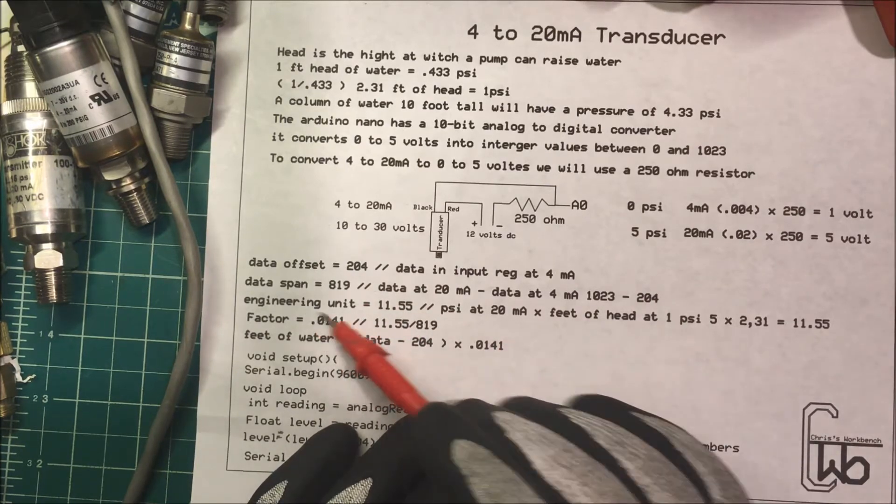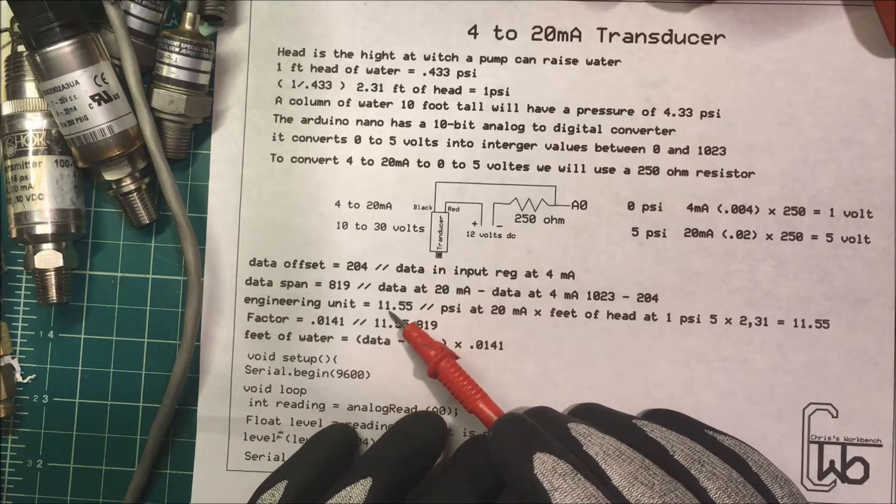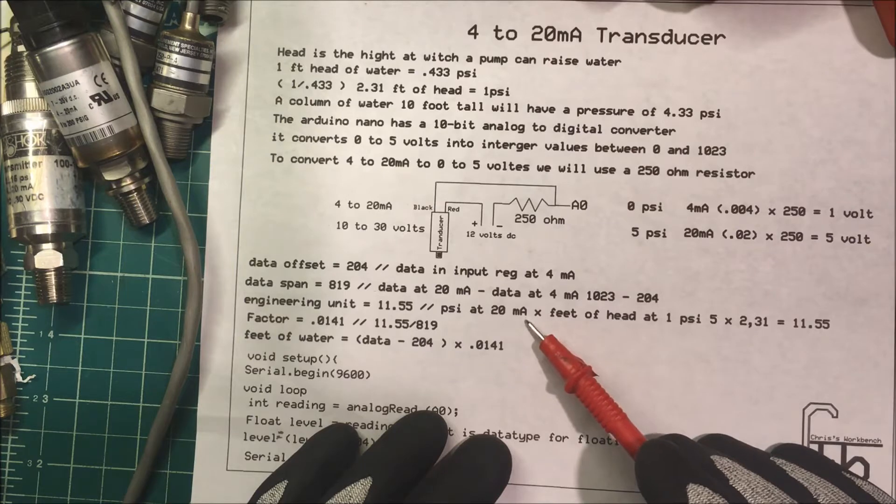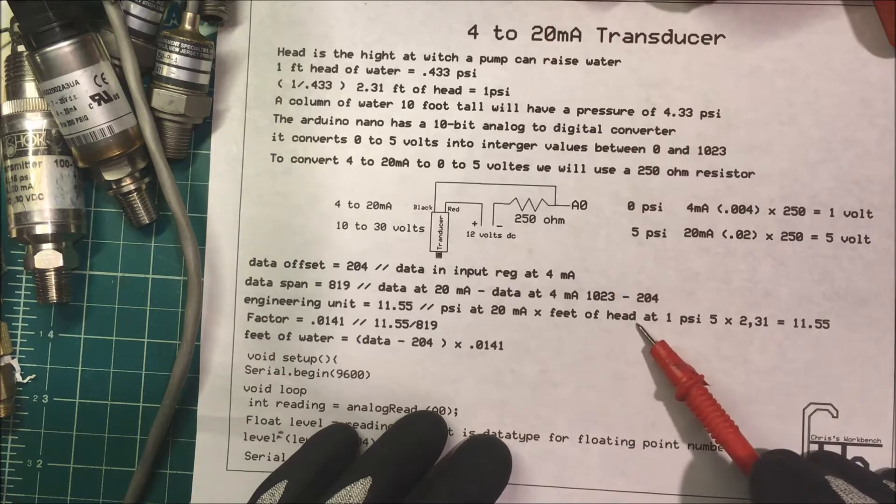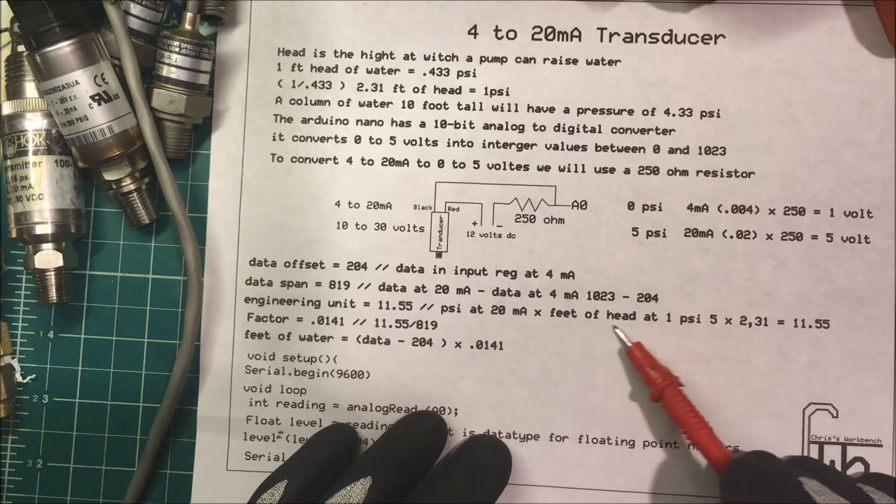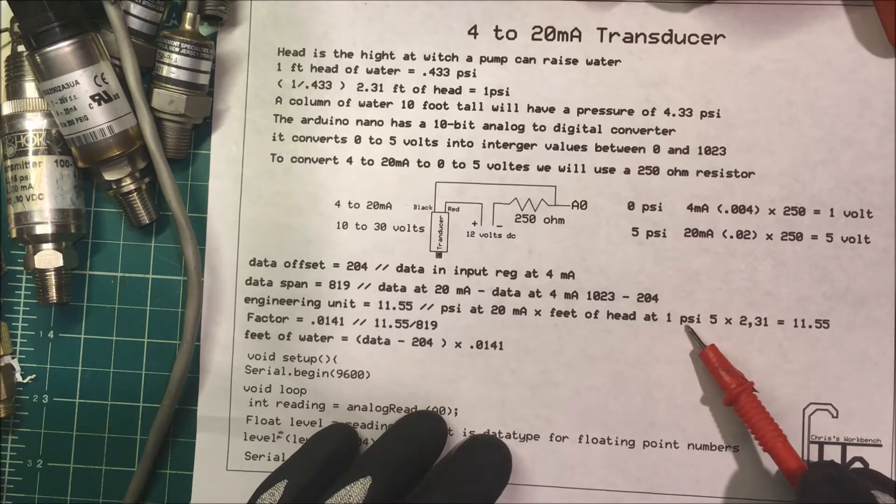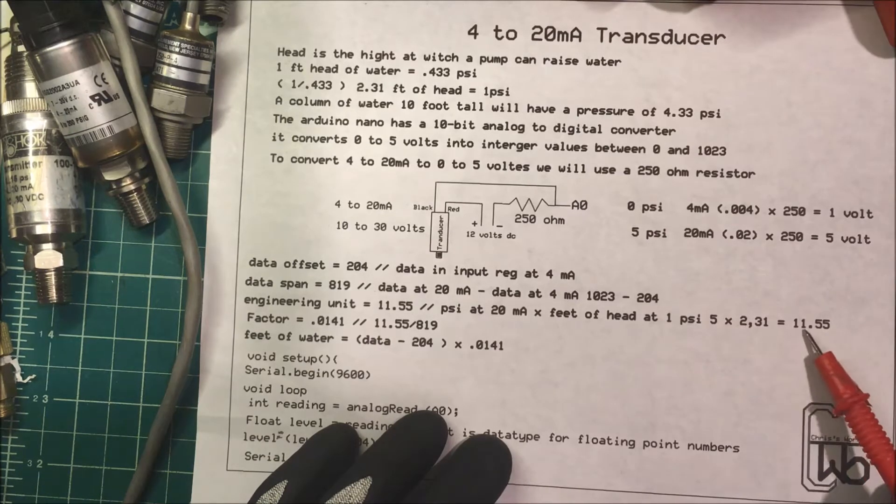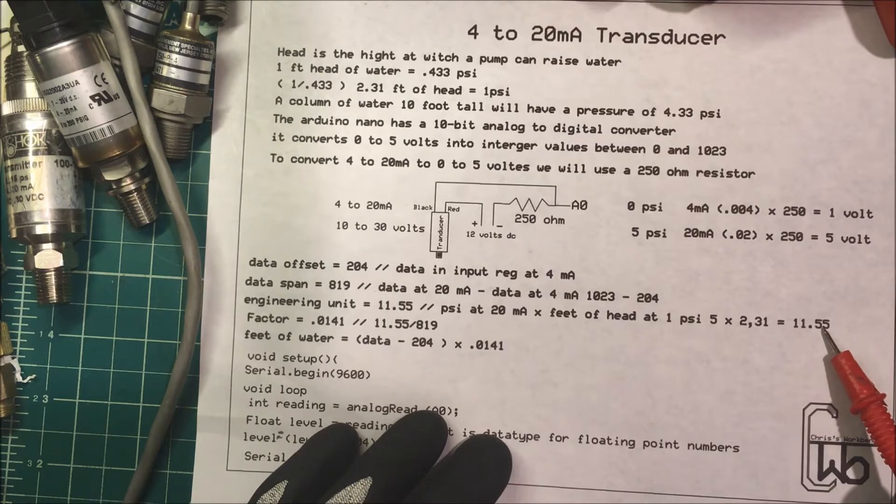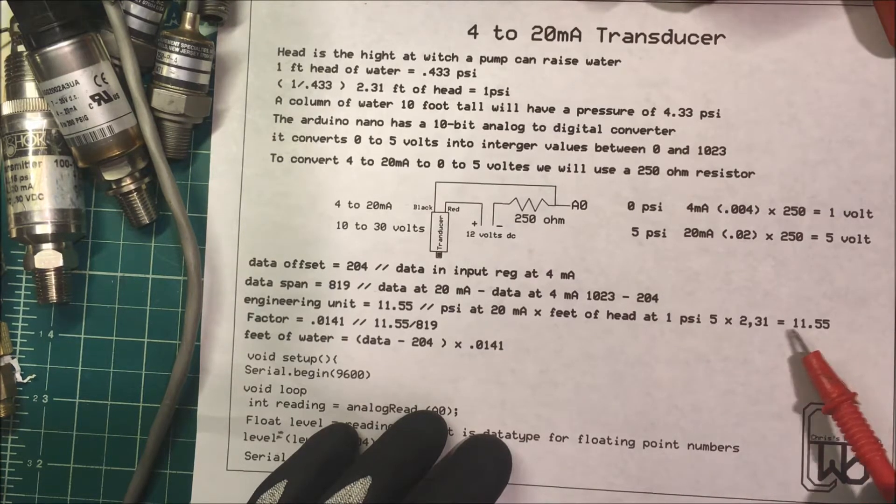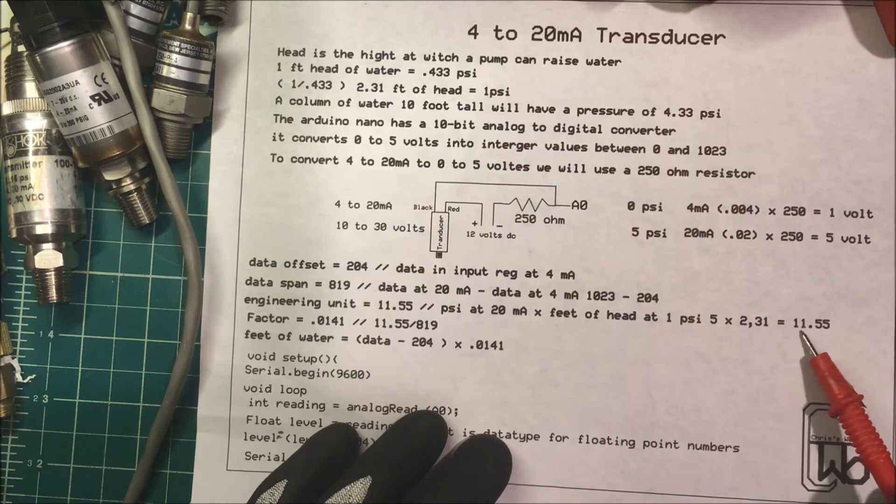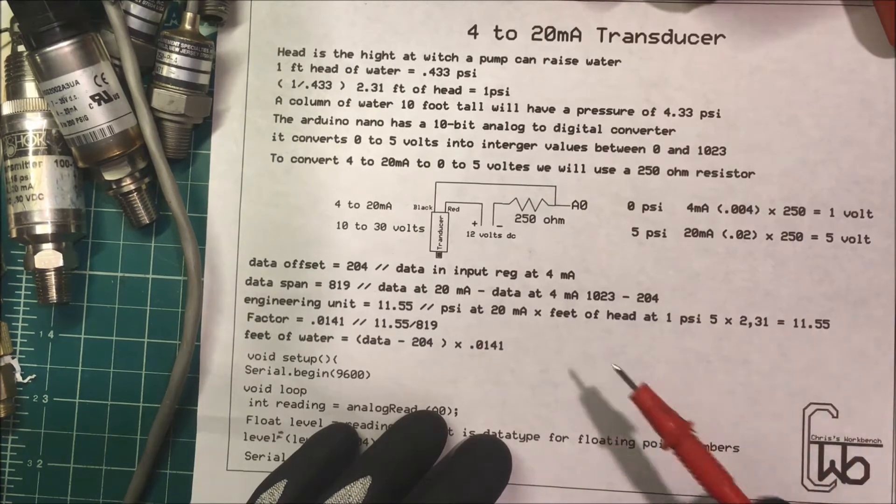Now we have an engineering unit and that's going to be 11.55. We get that by taking the pressure at 20 milliamps, which is going to be 5 times the feet of head at 1 psi. So feet of head at 1 psi is 2.31, so we take 5 times 2.31, which equals 11.55. Now at 5 psi it'll show us that we'll have a level of 11.55, a column of water that's 11.55 feet tall.